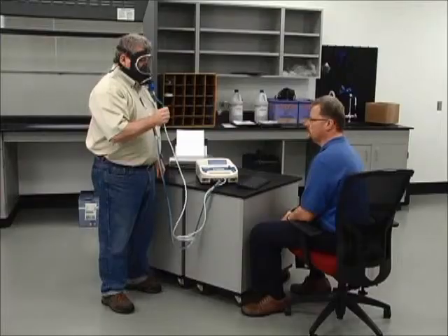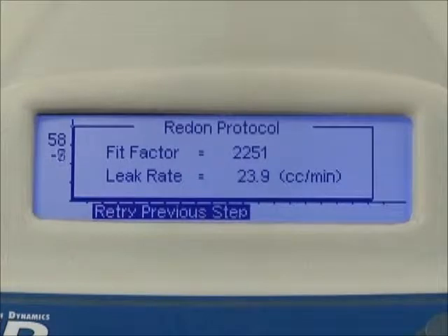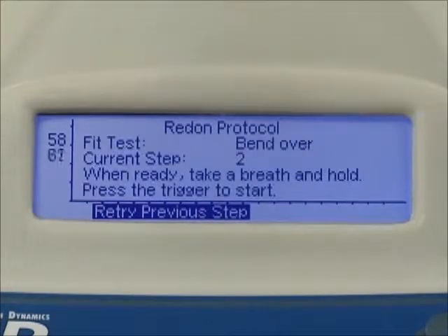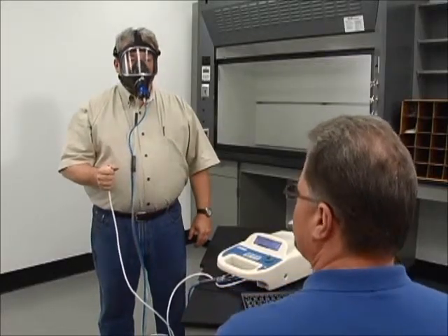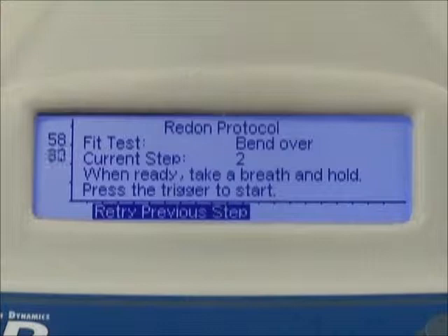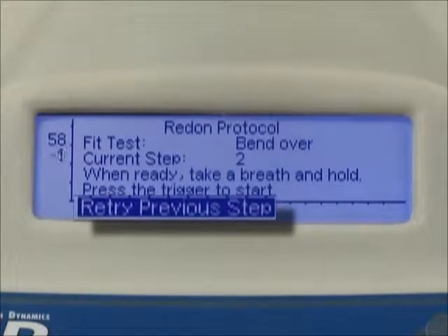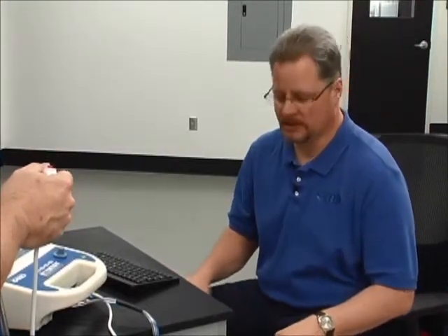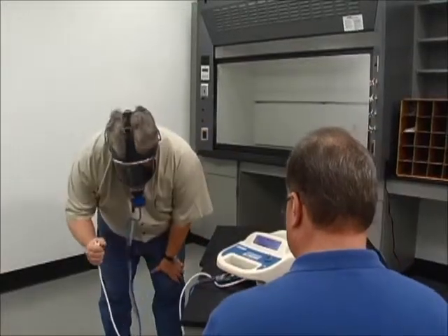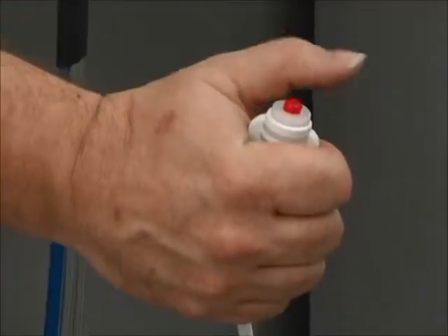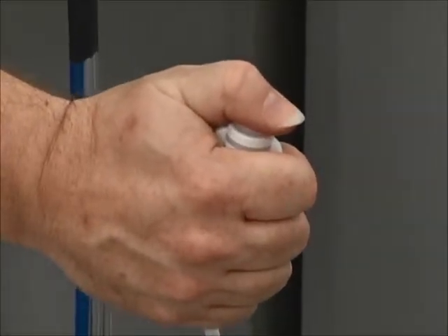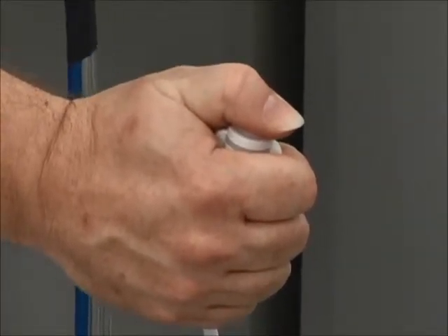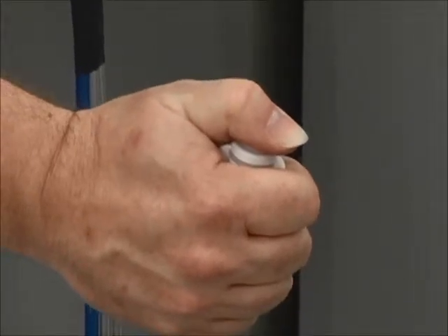If the test has met the minimum passing criteria, including a minimum passing fit factor, the operator will be prompted to begin the second step of the protocol. If for some reason the operator wants to redo the previous step, he may select Retry Previous Step. Read aloud the instructions on the fit tester to bend over and hold breath. The subject will bend at the waist and face the floor, allowing gravity to pull on the mask. He will then take a breath and press and hold the trigger button. Hold for 8 seconds and release the button, just as in the first step.